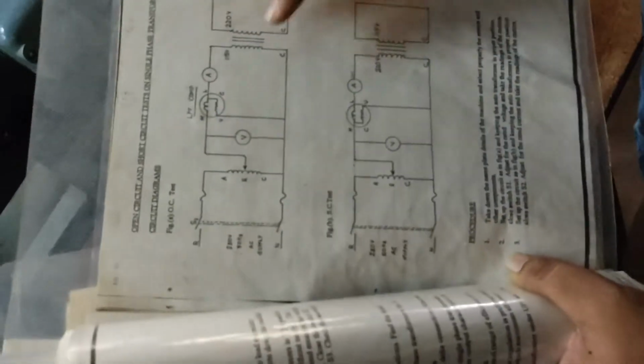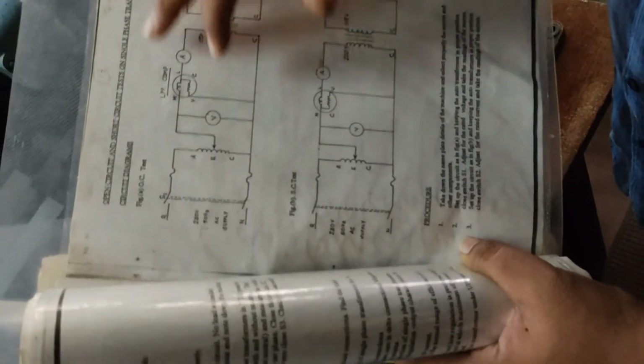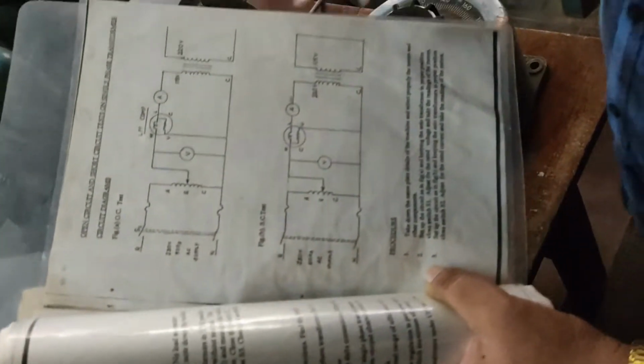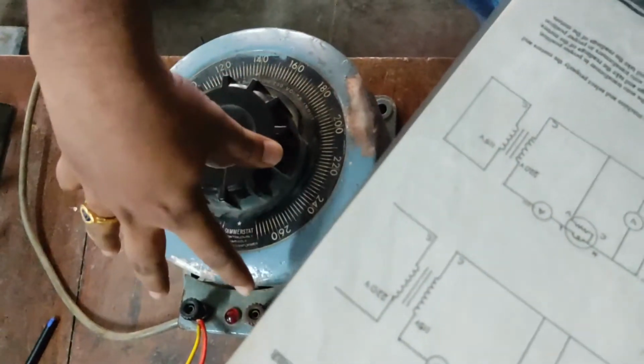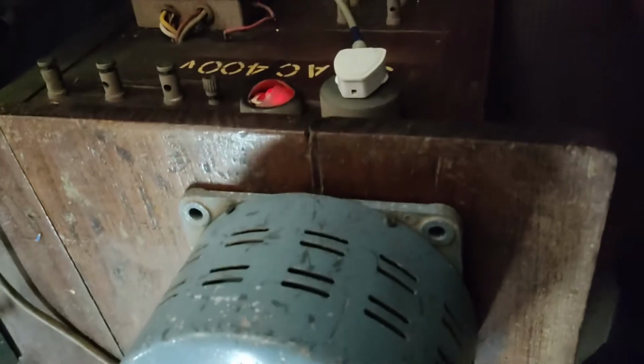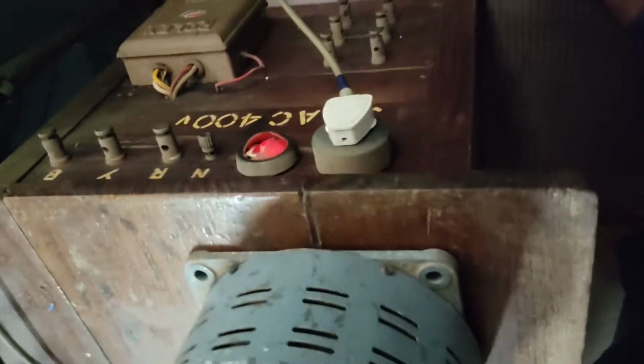So now we have to come to the diagram. To give the supply to this transformer, a single phase variac is required, because this is a single phase transformer. The single phase variac we can take from here. The supply can be given phase and neutral to this auto transformer. On the auto transformer, we can connect the supply here, give the supply, turn on the switch here, and we get the supply here.